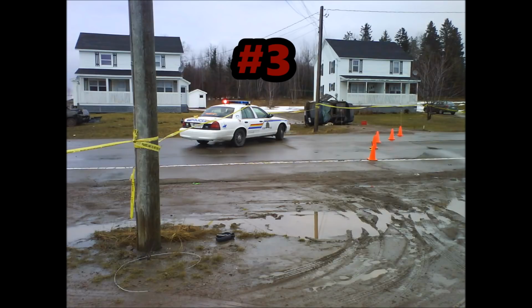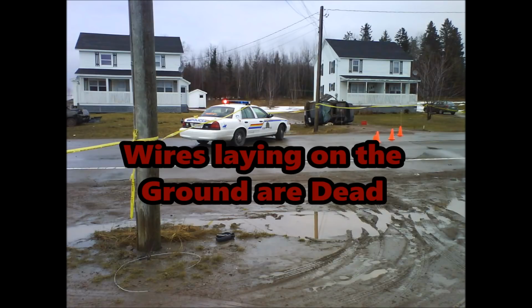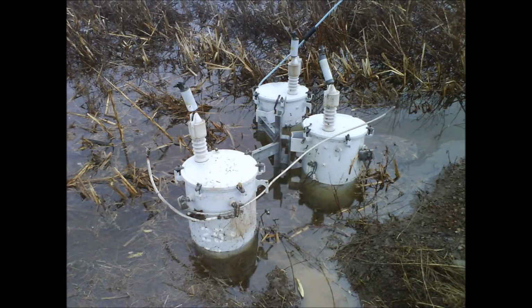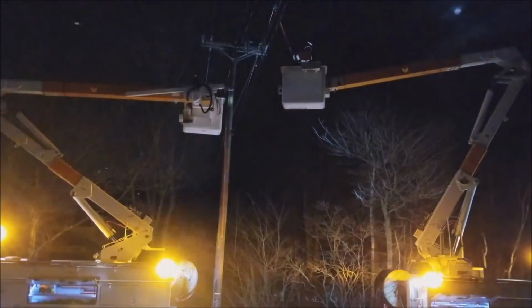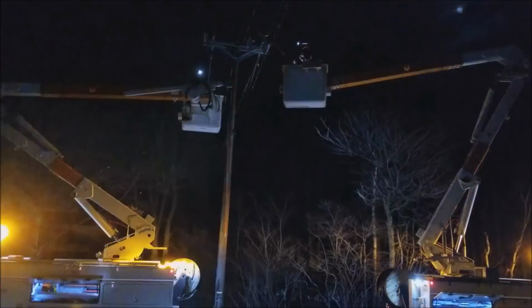Number 3. Wires laying on the ground are dead. No, don't ever assume that. Even a properly trained lineman will not touch down power lines until they are properly grounded. Even if the line is tripped out, it is possible to receive a lethal shock from the induction, backfeed, or simply a line holding its charge.